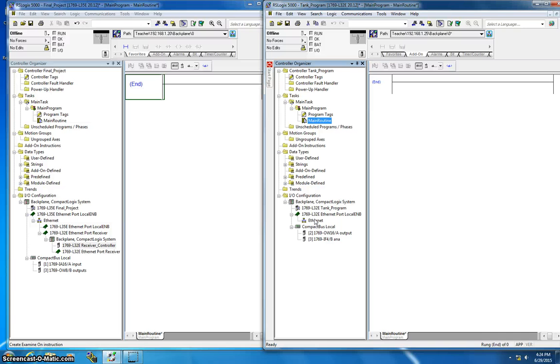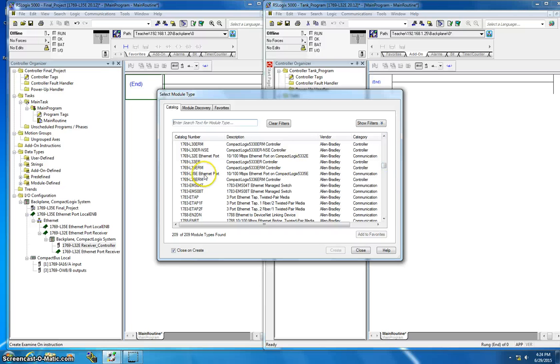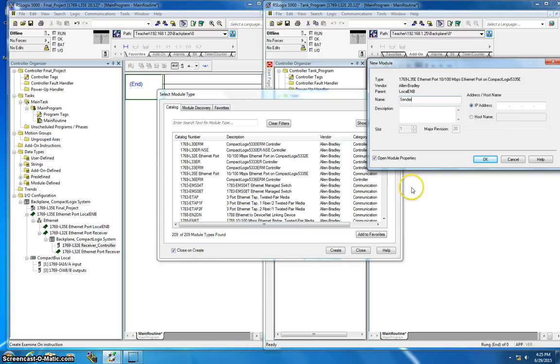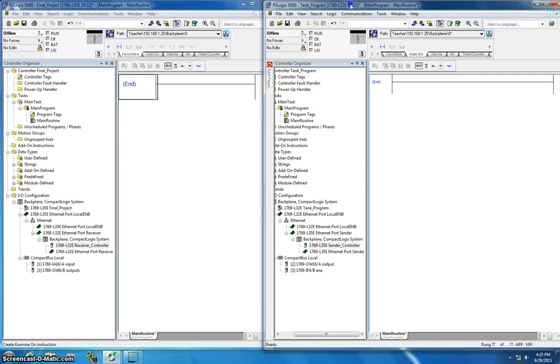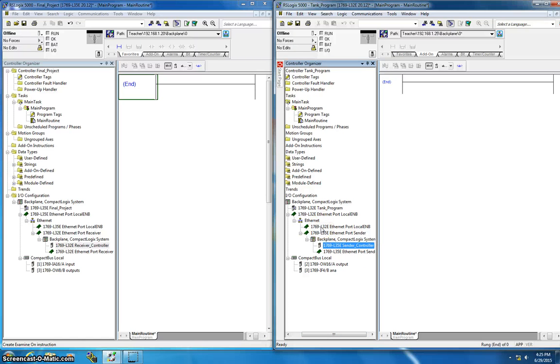Now I need to do the same thing on the L32E side — this is the receiver and the other is the sender. I right-click and select new module, going through the same basic steps but this time looking for an L35E, not an L32E. Major revision is again 20. I name it 'sender' and enter the IP address 192.168.1.20, which is the IP address for the L35E. One, two, three, four, five drops — networking is good.